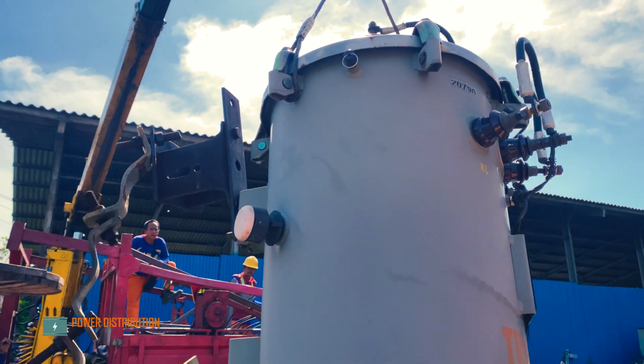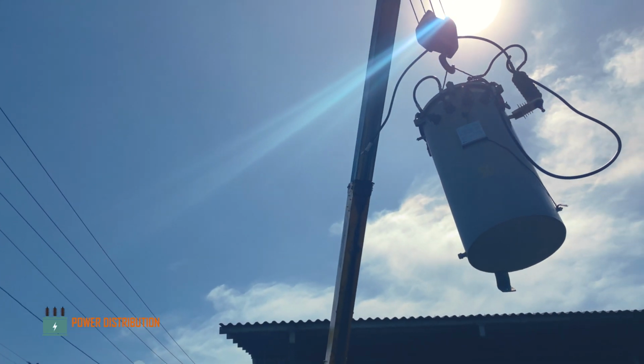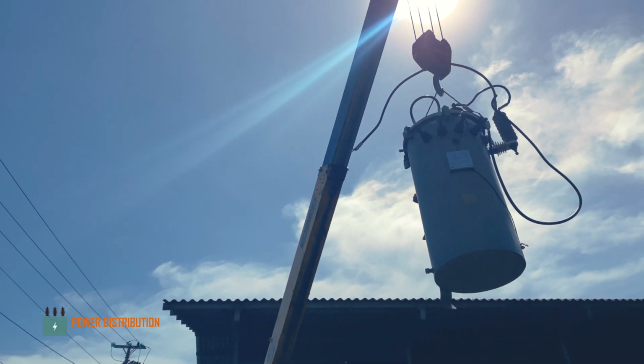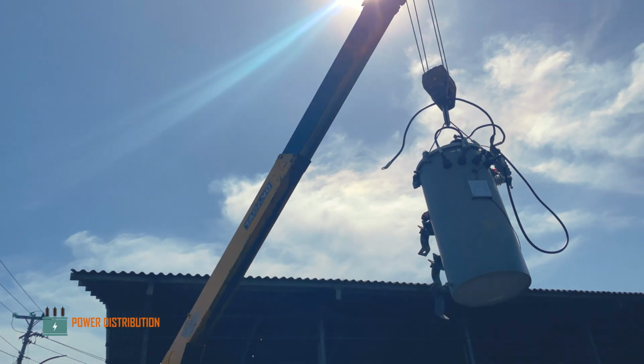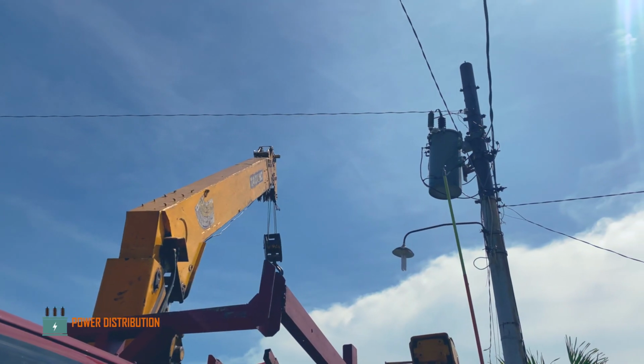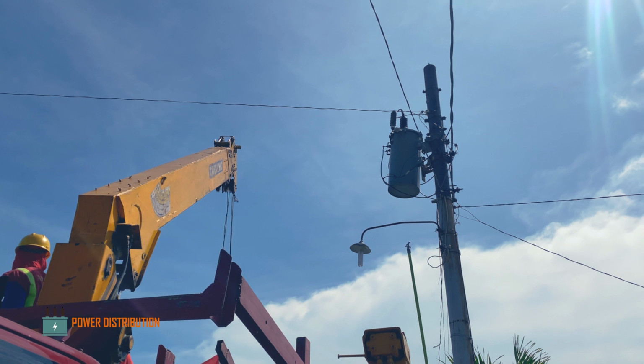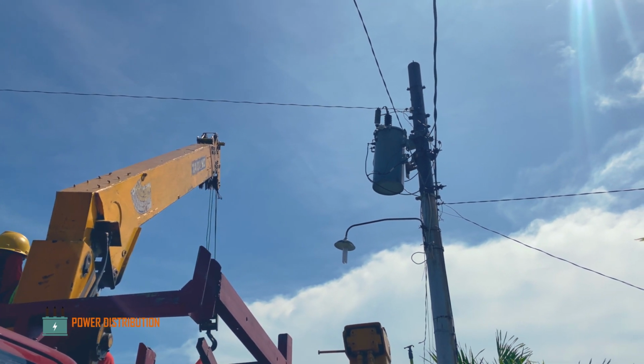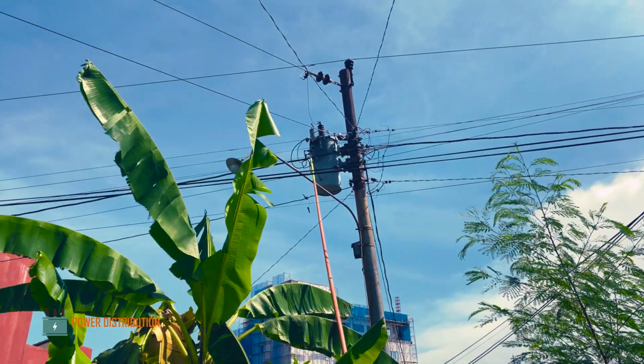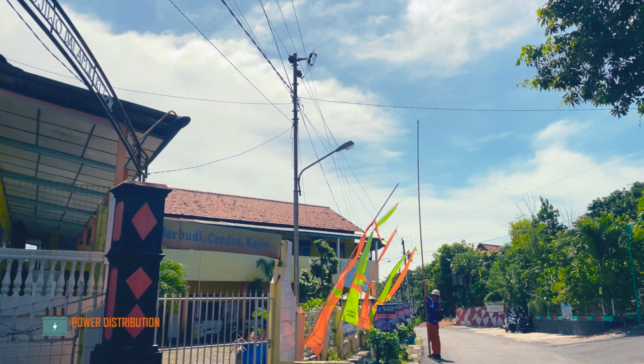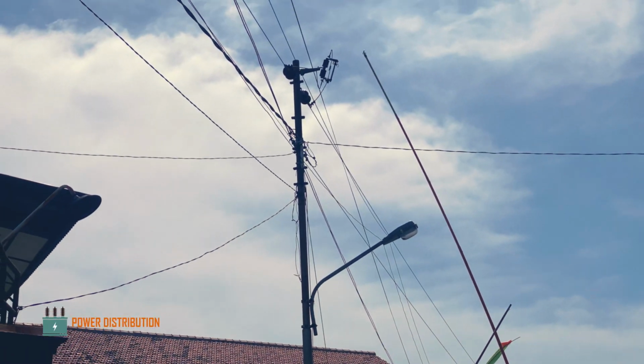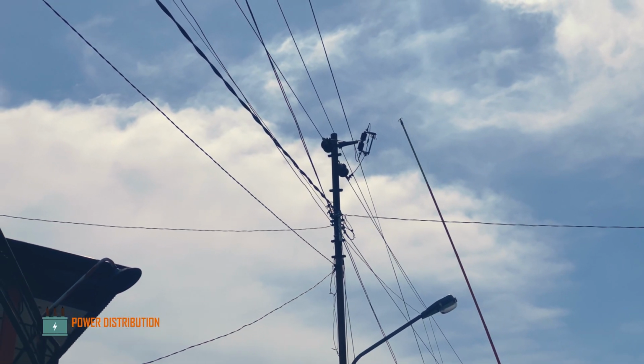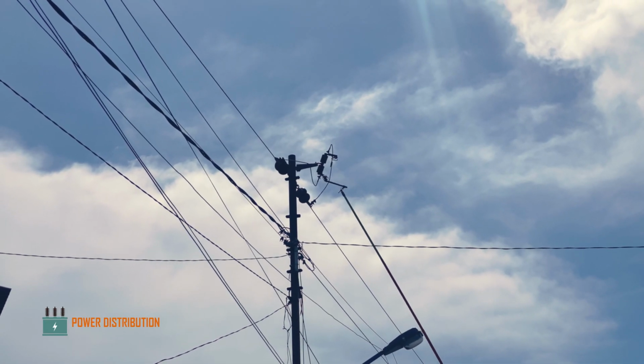First, the crew prepares and picks up the transformer from the warehouse. On site, before the crew de-energizes the line by opening the line cutout, they pull some breakers on a nearby transformer to reduce load currents. And only then, they open the main cutout to minimize arcs and fire hazard.